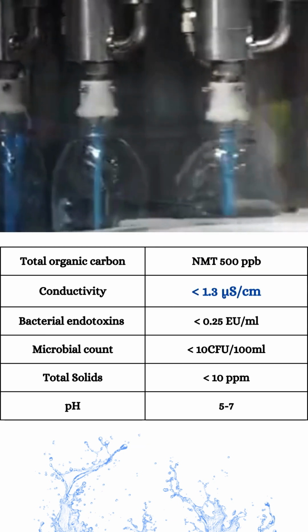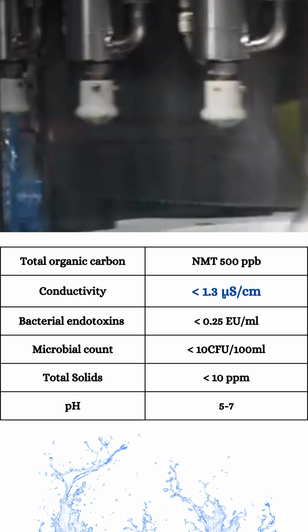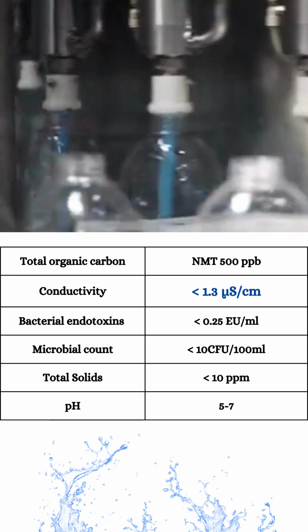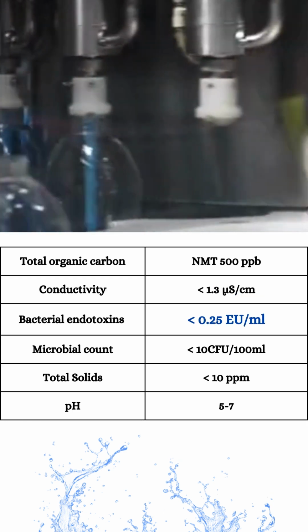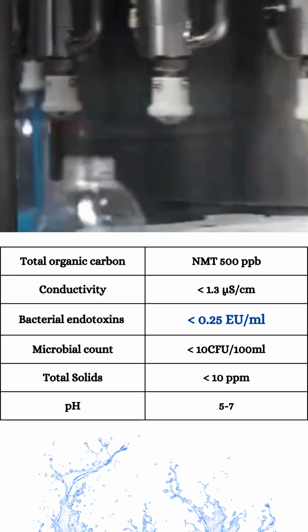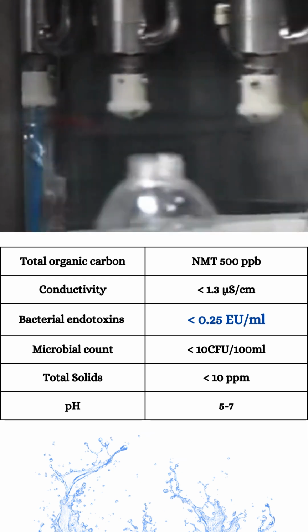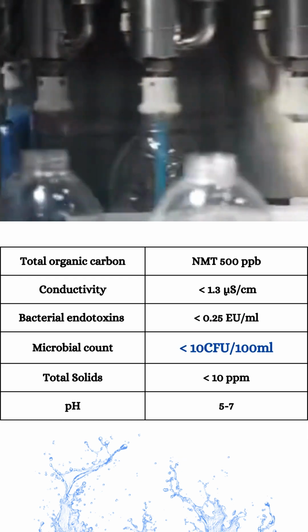Total organic carbon must not be more than 500 parts per billion. Conductivity should be less than 1.3 microsiemens per centimeter. Bacterial endotoxins must be below 0.25 endotoxin units per milliliter.